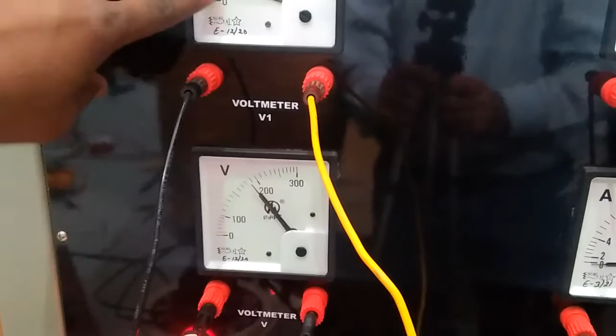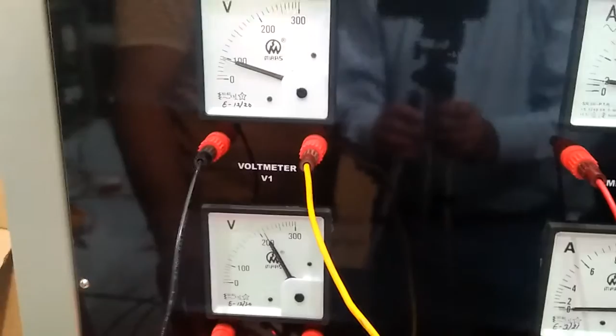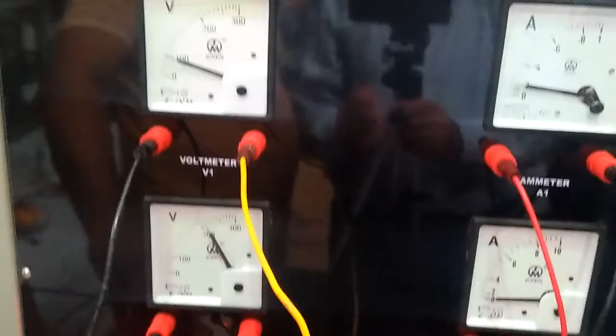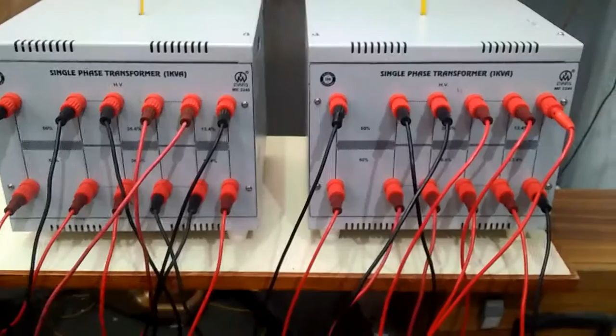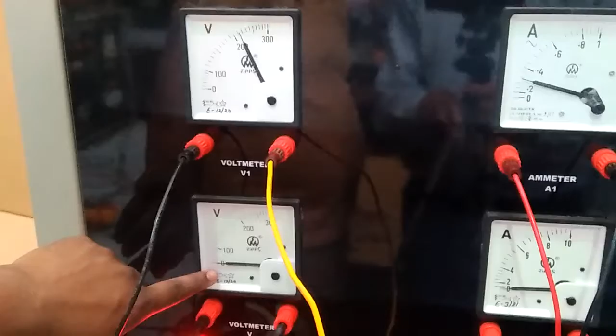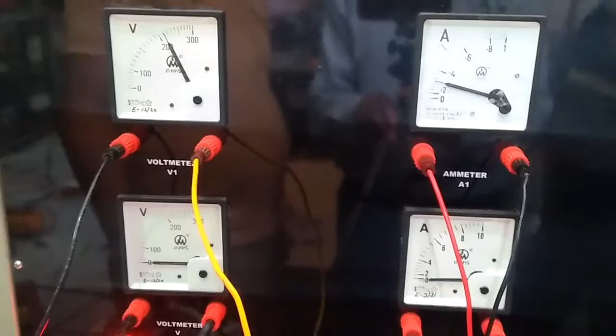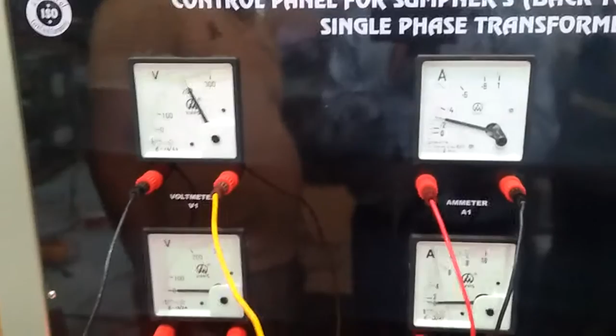As we have shown over here, this is the connection in additive manner, because the input is 100 and the output is double the input. So we have to change the connections, and minimize the variac. To make the subtractive polarity, we have to change any one secondary output. Again check the polarity. Now increase the input supply and the output voltage is 0. That means it is in subtractive polarity connection for the transformer. Now further we will proceed.